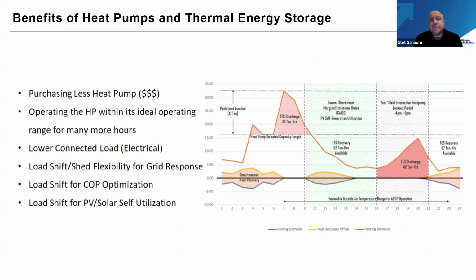So when you're pairing heat pumps with thermal energy storage, you can buy a lot less heat pump and let the storage ride those peaks much more cost effectively. We had a project where the storage was cheaper than the heat pump module, so we added more storage. It also lets your heat pump run when it really wants to. Smaller connected load means less infrastructure upgrades, which means lower first cost.